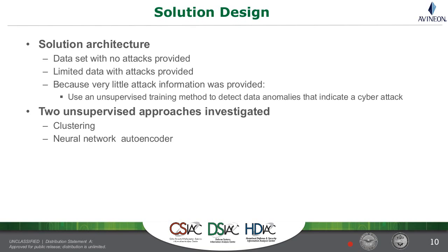Because we had very little attack information, we elected not to use a supervised learning technique. We felt like an unsupervised approach was going to be better. The primary difference between a supervised approach and an unsupervised approach: if we had a data set where there was a lot of attack information, we could have trained it to recognize very specifically those attacks. But because we had so few attacks, we felt like that wouldn't yield a solution. Instead, we just wanted to characterize the normal system behavior, and then it would detect anomalies in how that system is behaving in a normal environment.